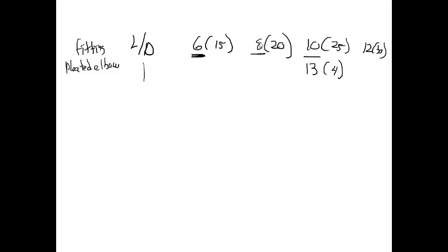Okay, so it would be the equivalent length at the associated diameter. Sorry, I don't know why that took so long for me to explain. I think I was looking at the chart and trying to talk at the same time and it wasn't working out. So if I have a pleated elbow at a 90-degree angle, that's what the first entry is, and I have a 10-inch duct, I would have the equivalent length of 13 feet. Okay, and that's basically how it is.